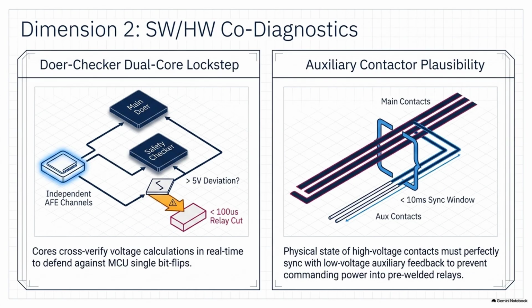So if that rogue cosmic particle happens to hit the exact memory address where the computer is currently storing the capacitor's voltage reading, the main processor, the doer core, might suddenly believe the capacitor is sitting fully charged at 800 volts, when in physical reality, it is completely empty. Oh my God. Operating on this corrupted data, the doer core would cheerfully command the main contactors to slam shut right into a dead short circuit, totally blind to the catastrophe it just caused. Because its brain was literally altered by a subatomic particle for a microsecond. That is both fascinating and terrifying.